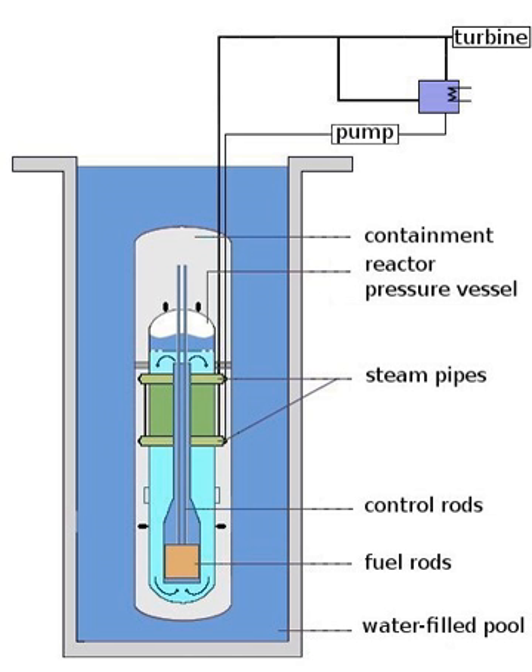In boiling water reactors, the fuel is similar to PWR fuel except that the bundles are canned — that is, there is a thin tube surrounding each bundle — primarily done to prevent local density variations from affecting the neutronics and thermal hydraulics of the nuclear core on a global scale. In modern BWR fuel bundles, there are either 91, 92, or 96 fuel rods per assembly depending on the manufacturer. A range between 368 assemblies for the smallest and 800 assemblies for the largest US BWR forms the reactor core. Each BWR fuel rod is back-filled with helium to a pressure of about 3 atmospheres (300 kilopascals).